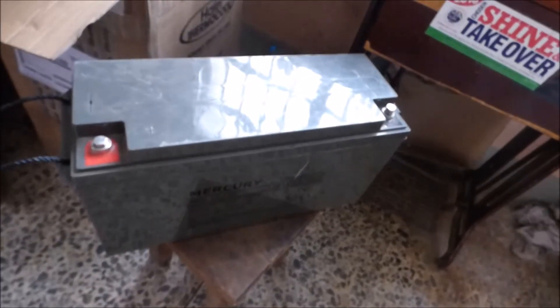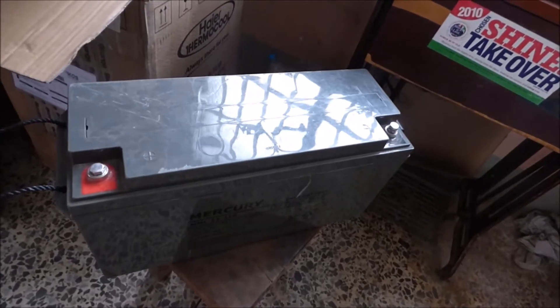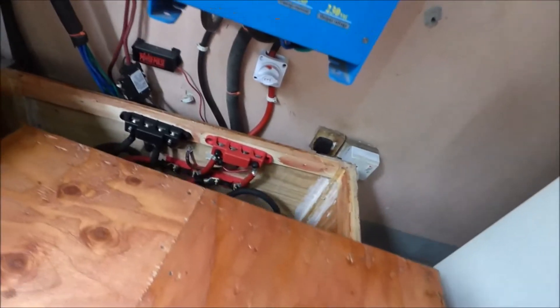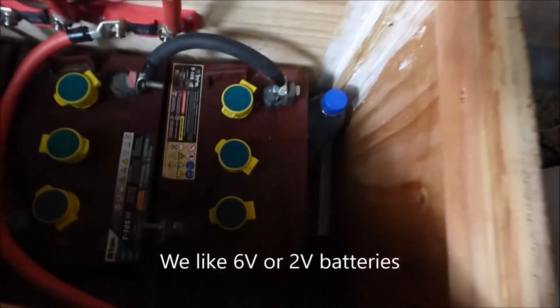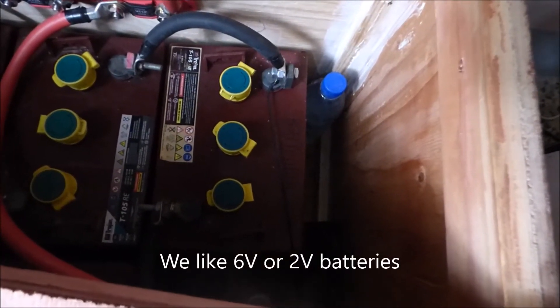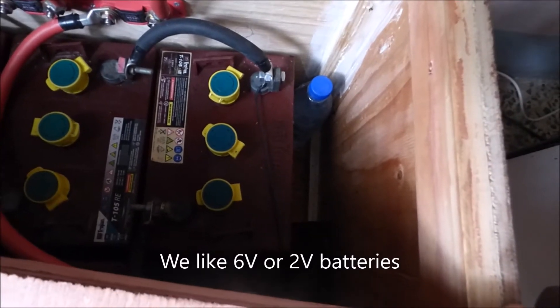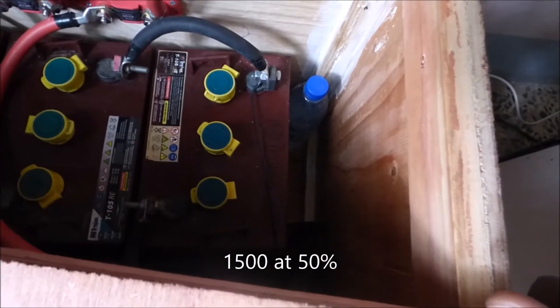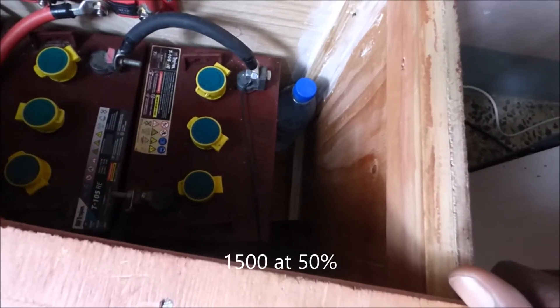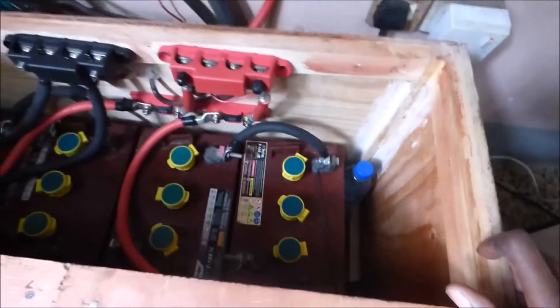400 cycles is a little more than one year. So if you discharge it up to 50 percent it'll last you one year; if you discharge it much less than that it'll last you longer than a year. Our batteries, on the other hand — we use flooded batteries and our preference are the Trojan batteries. These have a cycle life of 1,500 at 50 percent depth of discharge. If I discharge them even less they could give me a cycle life of about 3,000. Do that math — 3,000 divided by 365 — that is a huge number.